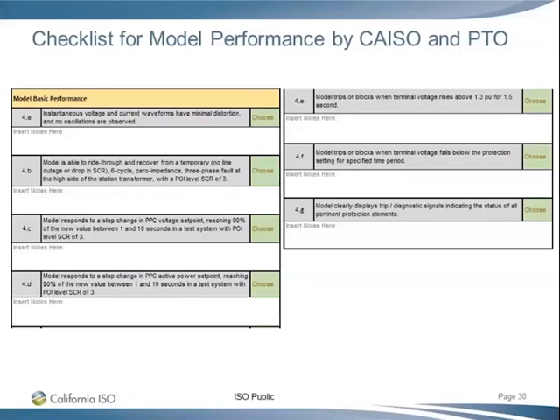The model responds to a step change in PPC voltage, reaching 90% of the new value. So this one we could say yes or no; both are valid. It says between 1 and 10 seconds, but actually what we are looking for is the actual response from the plant. If the Mod 26 report shows a duration longer than 10 seconds, then this should be longer than 10 seconds, as long as it matches the Mod 26. The next one is the active power set point step change. It says reaching 90% of the new value between 1 and 10 seconds in the testing with SCR equal to 3. Similarly, the answer could be yes or no. Bottom line, it should match the Mod 27 test.